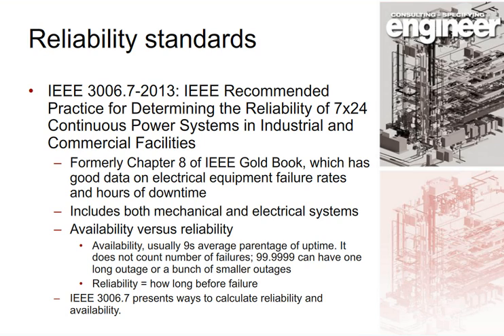There's an important difference between availability and reliability. When you see the nines — five nines, four nines — that's really referring to availability. It does not count the number of failures. A five-nines or four-nines facility could have one long outage or a series of ten-minute outages. Reliability is really how long something is going to function before you have any disruption to continuous operation. IEEE 3006.7 presents detailed calculations to actually determine reliability of both electrical and mechanical systems.